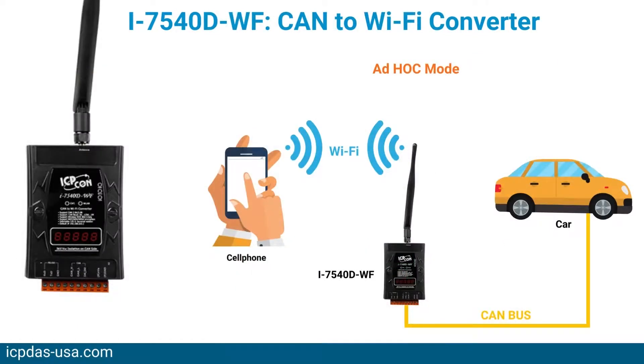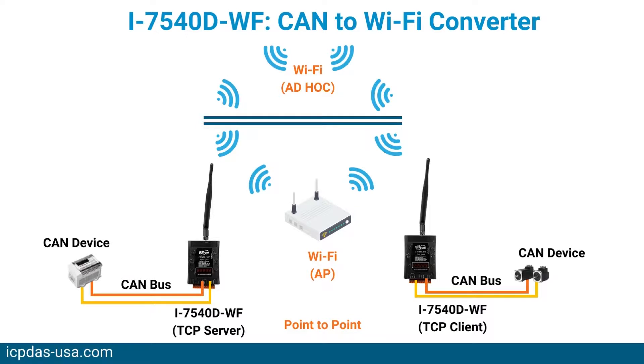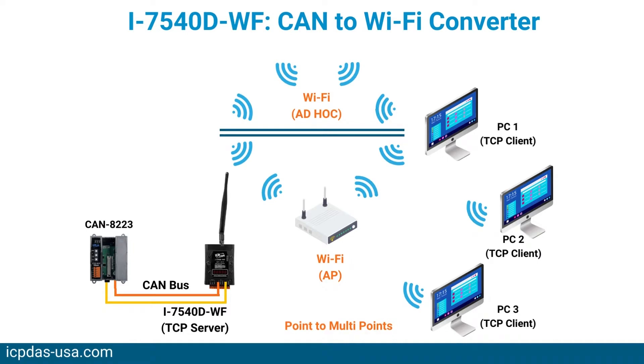The I-7540D-WF supports wireless transmission of CAN data between various CAN networks or a CAN network with a WLAN network. It is highly suitable for connecting mobile or stationary CAN networks and is often used for short ranges up to 100 meters. There are two operating modes: the access point mode and the AD-HOC mode. In access point mode, the data connection takes place over one or several WLAN access points that are often part of the company's internal IT infrastructure. In AD-HOC mode, a direct connection is established between a single I-7540D-WF device and a PC or laptop.